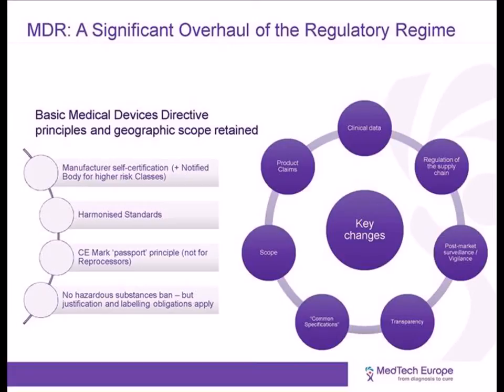Reprocessing of single-use devices is in principle banned under the MDR, unless national laws permit the activity. Where the activity is permitted at national level, the MDR obligations of manufacturers will apply to the reprocessors. And the new legislation also regulates health institutions like hospitals and clinics that reprocess single-use devices, whether they do so in-house or through third-party reprocessors.